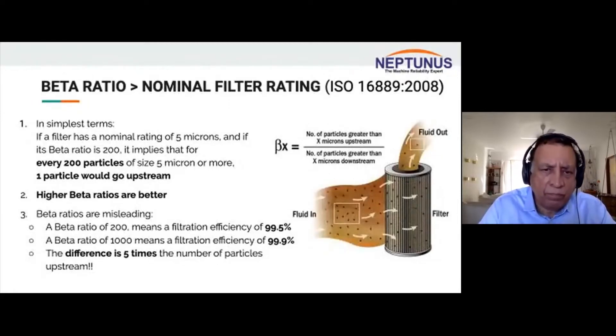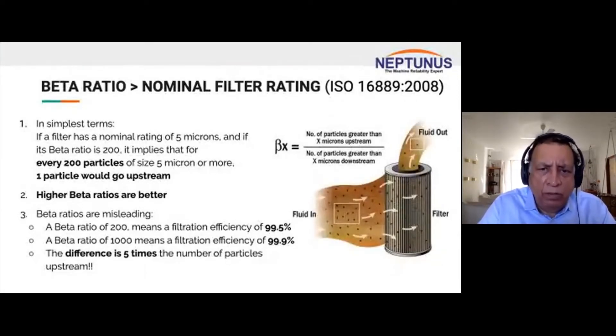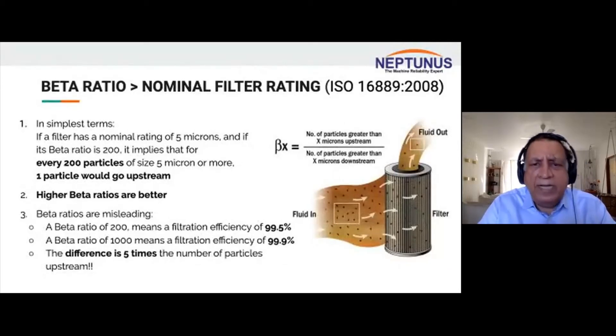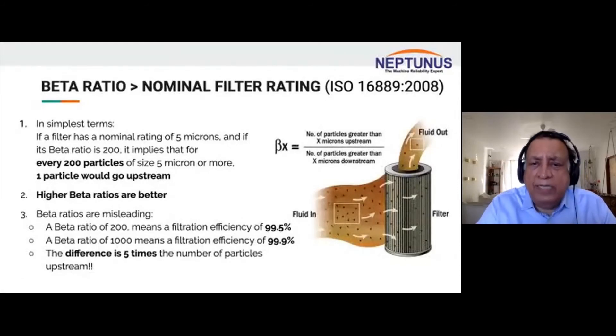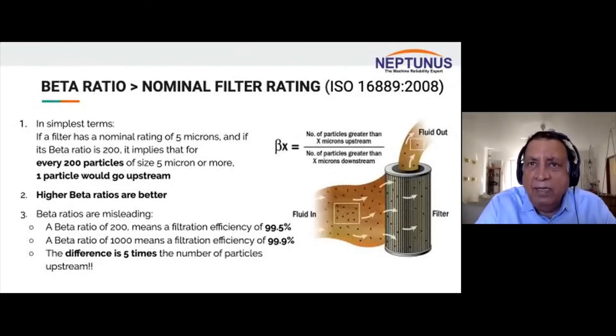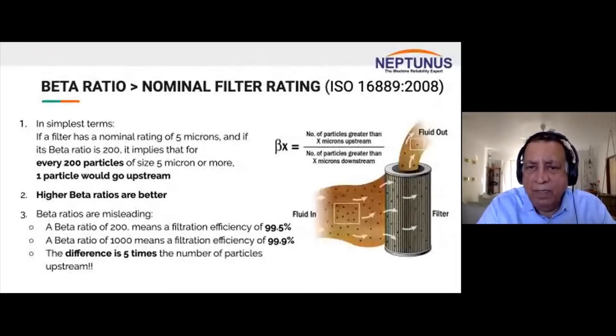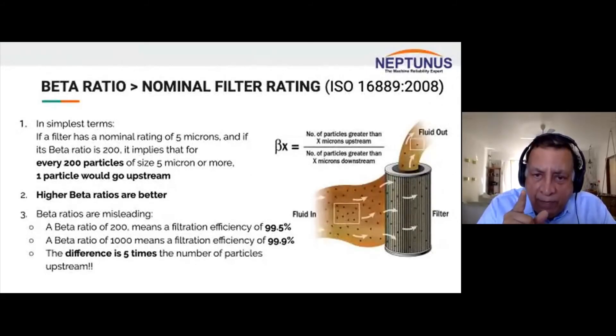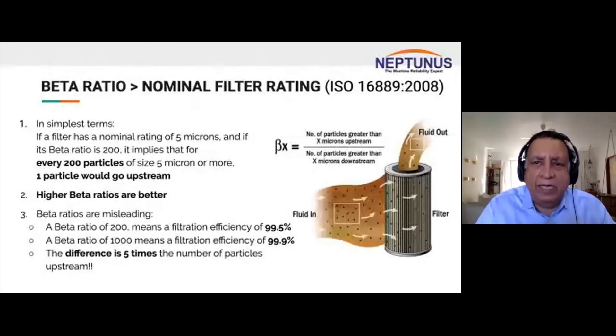Beta ratios can be misleading. A filter manufacturer might tell you their filter has a filtration efficiency of 99.5%, which corresponds to a beta ratio of 200, while a beta ratio of 1000 means 99.9% efficiency. The jump to 99.9% sounds only slightly better than 99.5%, but the actual difference is five times fewer particles passing through — that's a significant real-world difference.